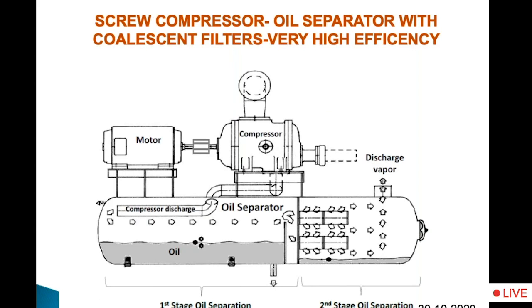The most efficient oil separator, if you ask me, is used in screw compressors. Why do screw compressors use a very high efficiency oil separator? Because the compressor is totally flooded with oil. Unlike a reciprocating compressor, in screw compressors the male and female rotors are totally immersed in oil, and therefore there is a lot of oil inside the compressor, and therefore you will see that in any screw compressor the oil separator is the biggest component in the system compared to reciprocating compressors. So you need very high efficiency oil separators so that minimum oil goes into the system.